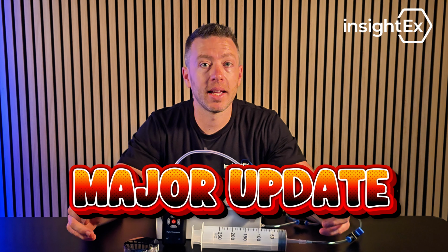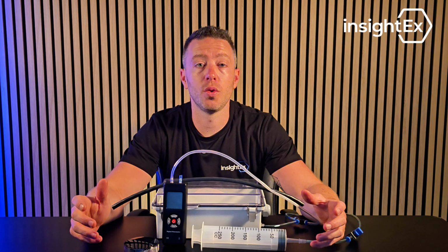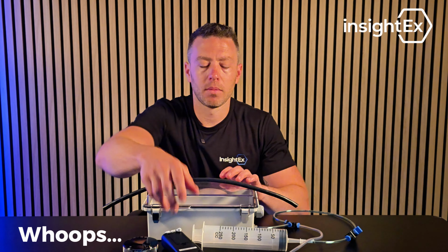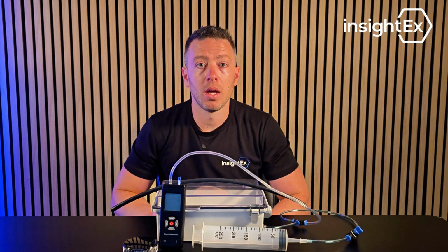There has been a major update to the cable and cable gland selection process for EXD, especially when it comes to deciding if you need a barrier gland or a non-barrier gland. And that's where this new Annex C pressure test comes in. There's still a lot of people that don't know about this test, so I really hope this helps.